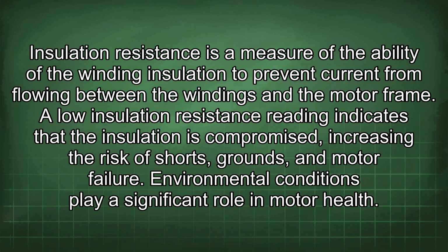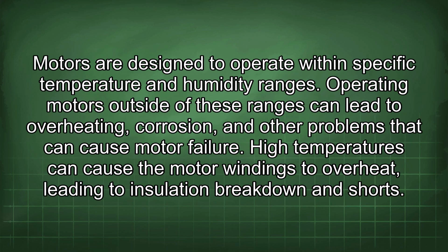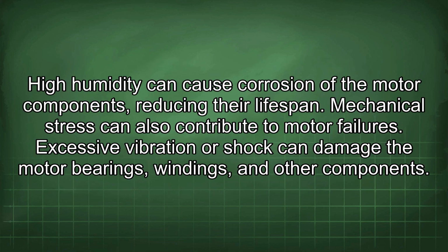Environmental conditions play a significant role in motor health. Motors are designed to operate within specific temperature and humidity ranges. Operating motors outside of these ranges can lead to overheating, corrosion, and other problems that can cause motor failure. High temperatures can cause the motor windings to overheat, leading to insulation breakdown and shorts. High humidity can cause corrosion of the motor components, reducing their lifespan.